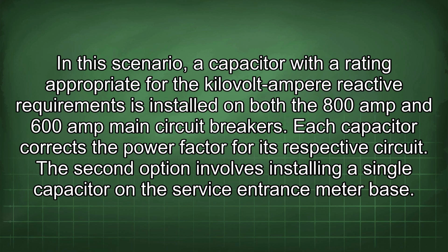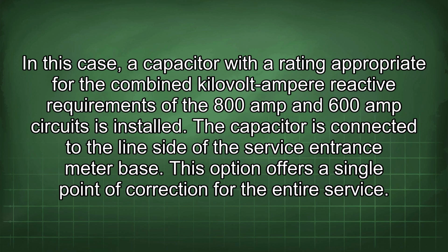The second option involves installing a single capacitor on the service entrance meter base. In this case, a capacitor with a rating appropriate for the combined kilovolt ampere reactive requirements of the 800 amp and 600 amp circuits is installed. The capacitor is connected to the line side of the service entrance meter base. This option offers a single point of correction for the entire service.